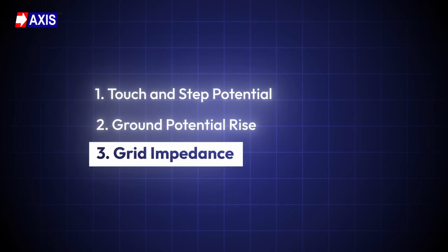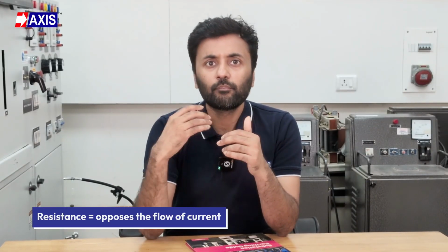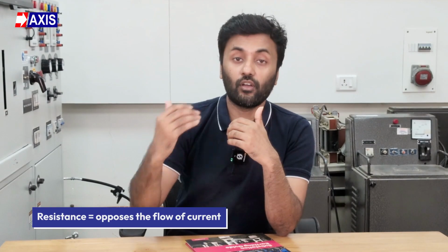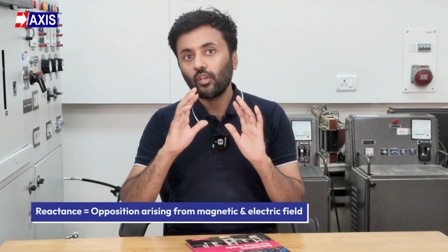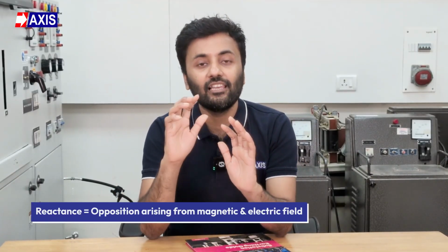Finally, let's move to the last risk, grid impedance. When the fault current tries to flow through the earthing grid into the soil, the grid does not let it happen freely. It opposes that flow, and that opposition is called grid impedance. It has two components. The first is resistance, which is a property of a material that opposes the flow of current. In the context of the grid, it comes from the conductive materials used and the contact between the grid and the soil. The second is reactance, which is the opposition that arises from the magnetic and electrical fields created around the grid and soil.